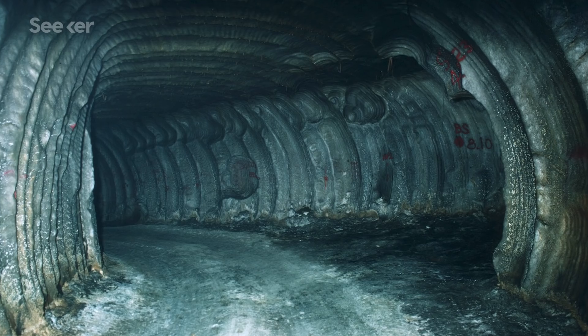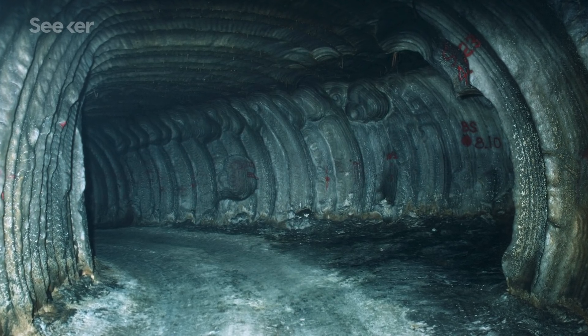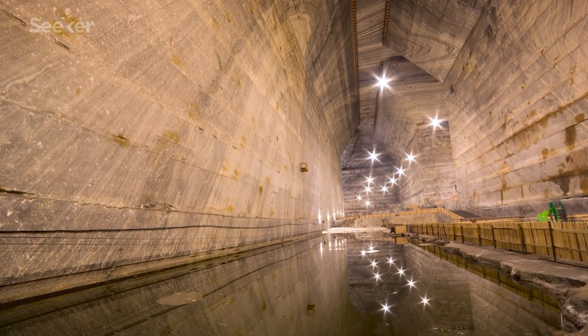But there are a few things holding it back. Conventional CAES systems require having a place like an existing or solution-mined rock cavern that's big and stable enough to store compressed air at a high pressure. This geographical limitation has meant that the technology can't always live where grid needs are greatest. Then there's the issue of conventional CAES systems not storing the thermal energy that's generated during charging. As air is compressed, it heats up, and as air expands, it cools down. If the thermal energy generated during compression isn't stored, a large chunk of energy during charging is lost to the atmosphere. To circumvent this problem, conventional CAES systems heat the air prior to expansion by burning natural gas, which not only deteriorates the system's efficiency, but seems utterly pointless if we want a greener system. For these reasons, CAES hasn't taken off — there's actually only been two plants built to date.